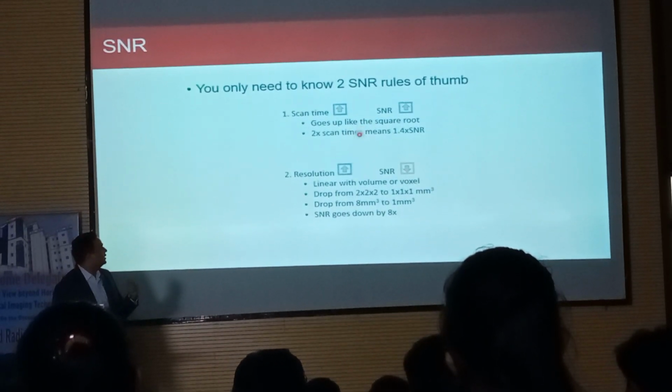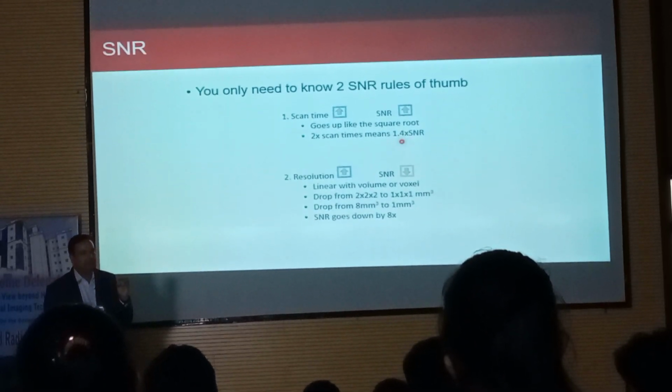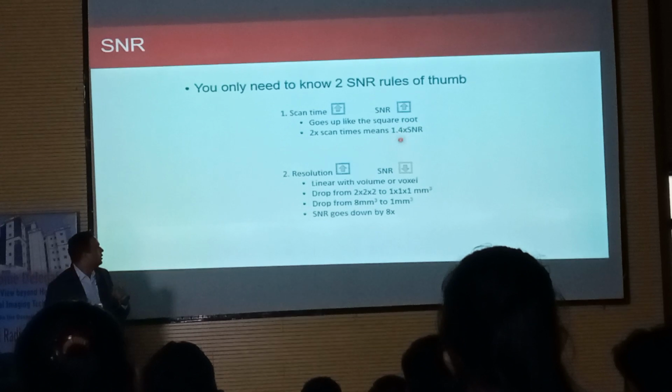However, it's not linear. So if you double the scan time, your signal to noise ratio will increase by 1.4 times, because this is the square root of 2.